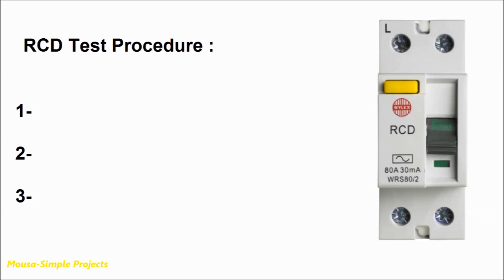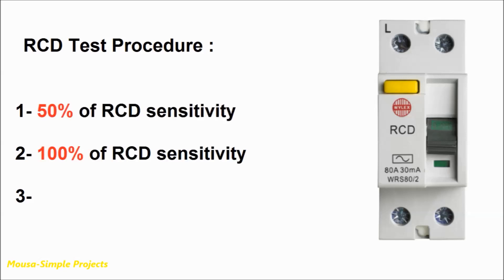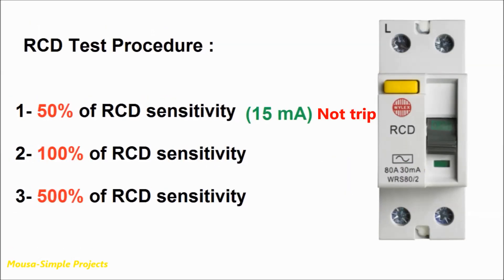We have to test it with leakage current of 50%, 100%, and 500% of its nominal sensitivity. Let's say we have an RCD with sensitivity of 30 mA. So we have to test it with 15 mA, 30 mA, and 150 mA of leakage current.